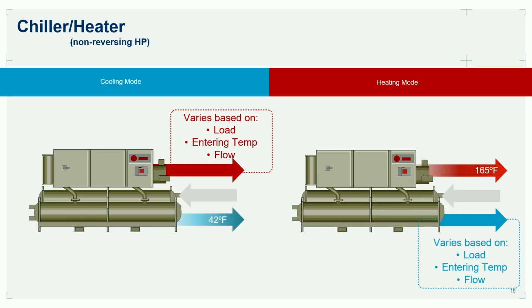Does anybody have a better name for the chiller heater out there? Because this is kind of what we're stuck on. It's a non-reversible heat pump—it's a ridiculous name, but I haven't found anything better. All chillers can be heaters; we're just focused on what's coming out the back end. With traditional equipment, put a different gas in it, we get up to 250 degrees out of a screw chiller—that's insane. What do you mean it's a chiller? Well, it's a chiller heater, I guess. So if anybody's got a better name for that, I'd love to talk through it.